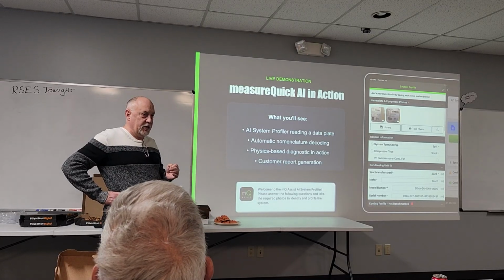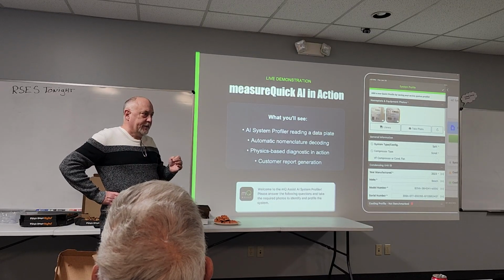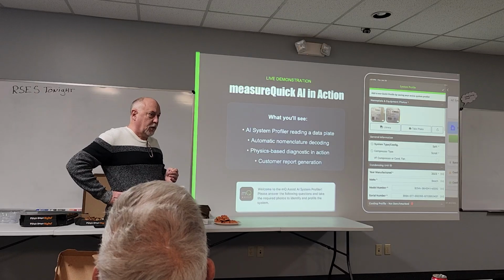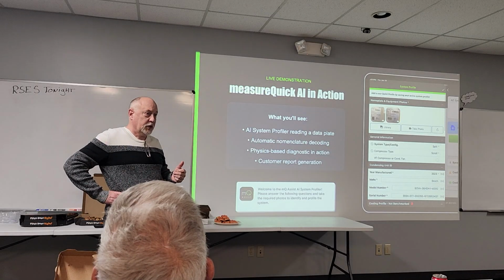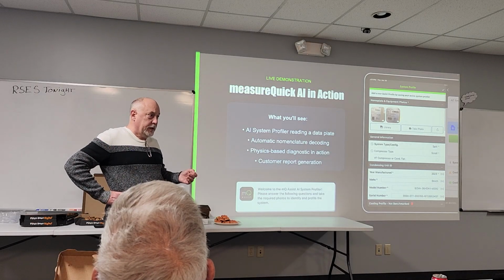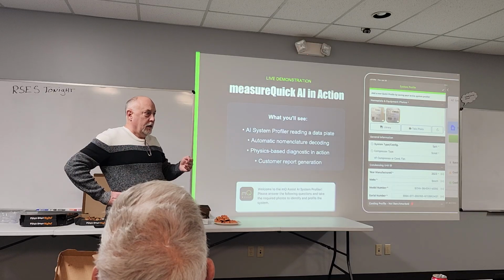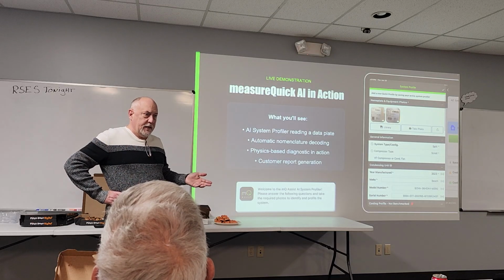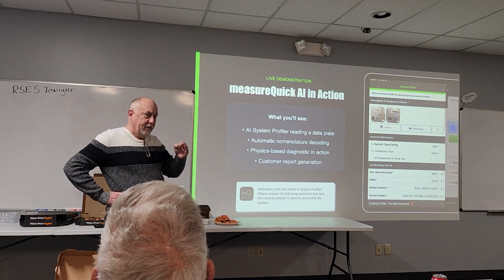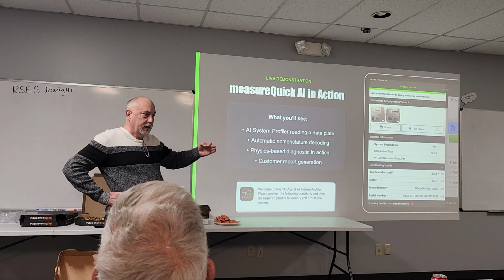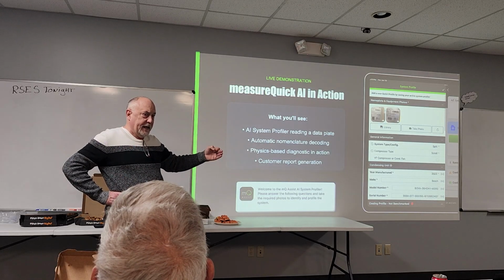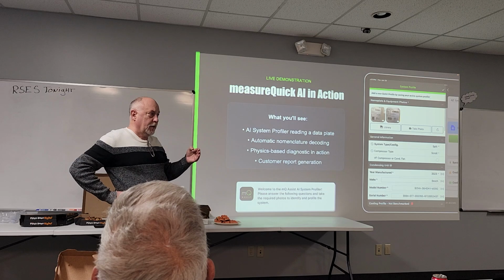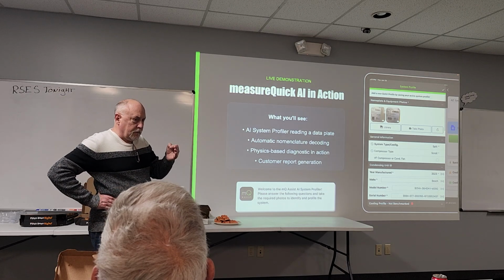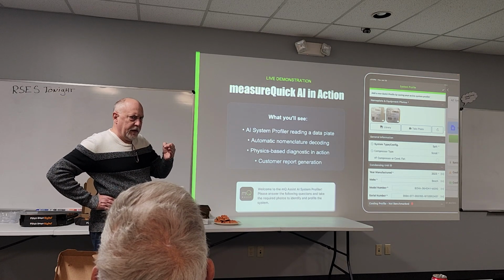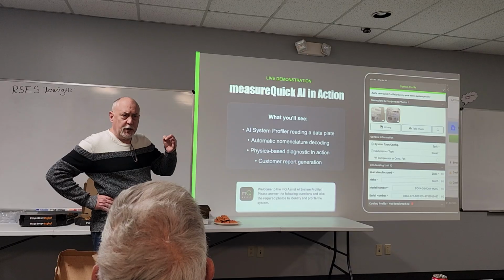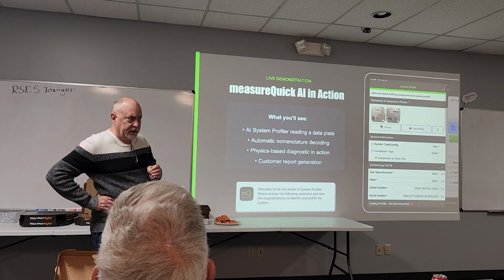Yeah, accurate information, right. If you're a service manager and you call somebody, some of the most important things you can tell me are what's the make, model, and serial number, what's the target subcooling on the data plate, what's the rated steam pressure, whatever you want to ask. That information about that unit helps us a lot to actually provide an accurate diagnostic. So what happened was we went from this very broad information to extremely granular information about units.